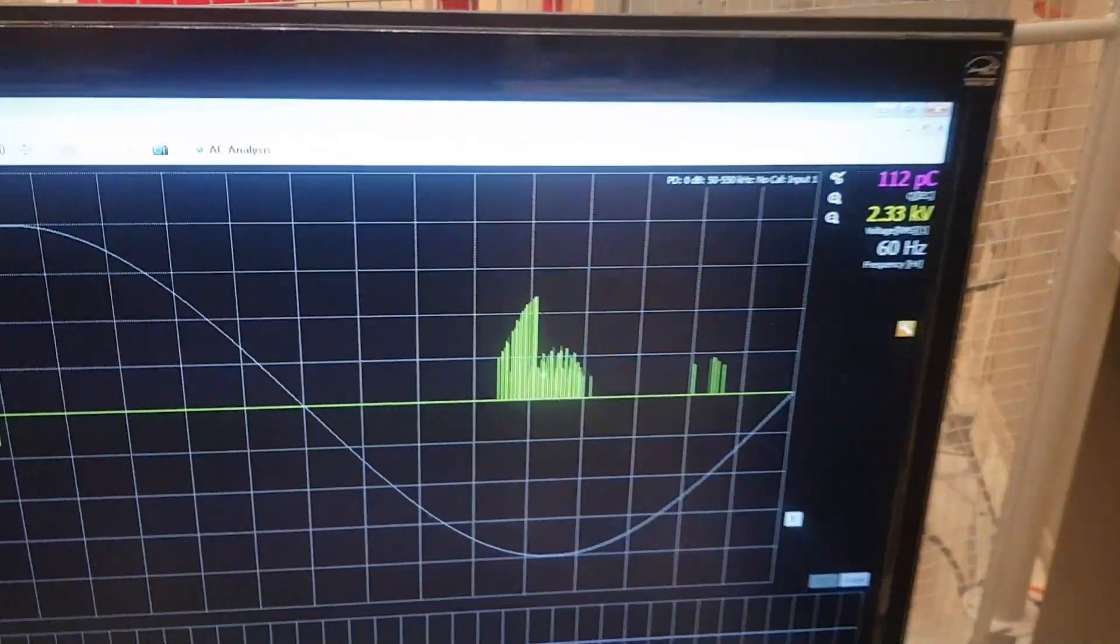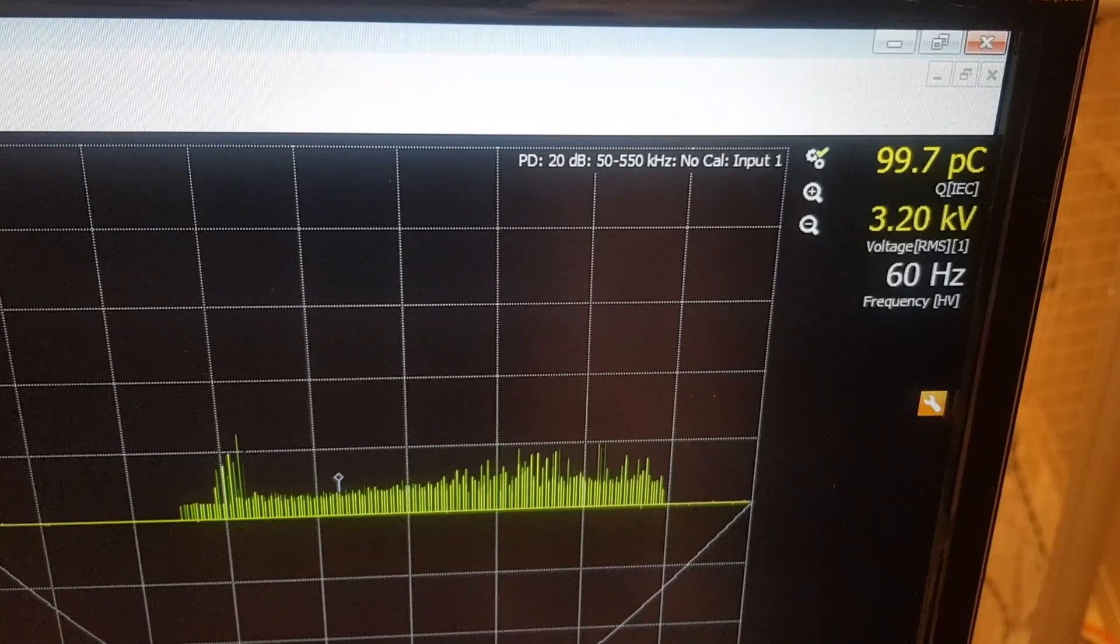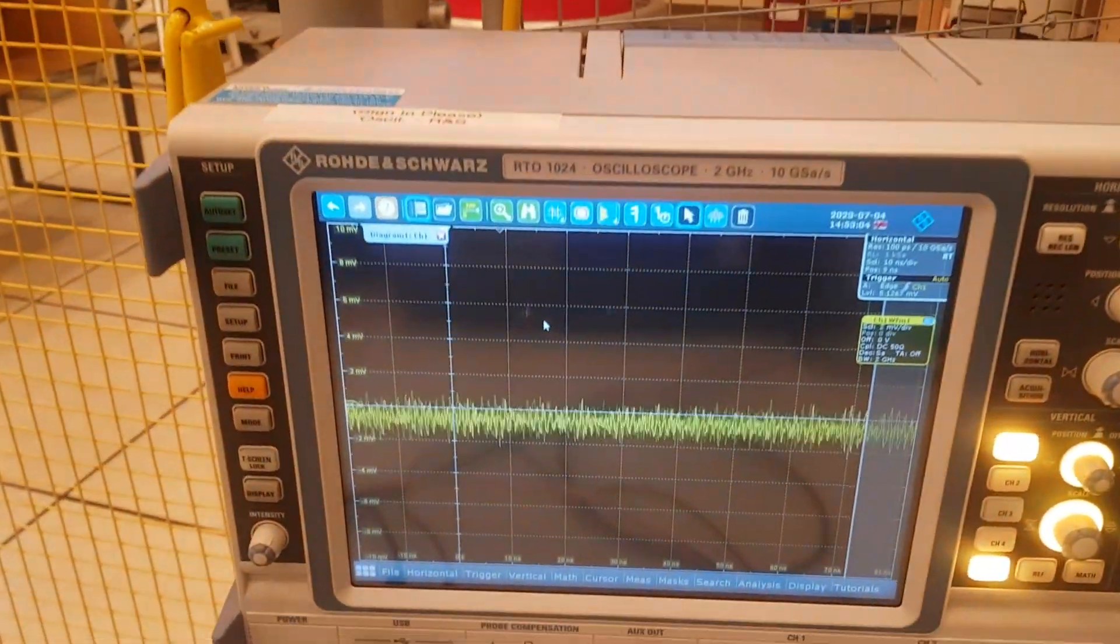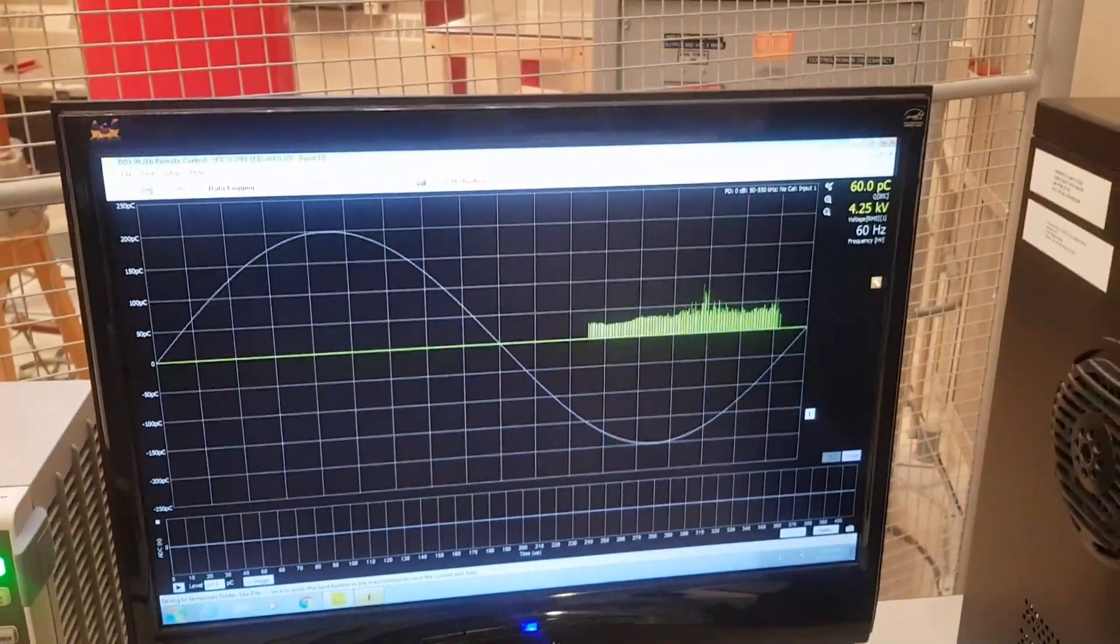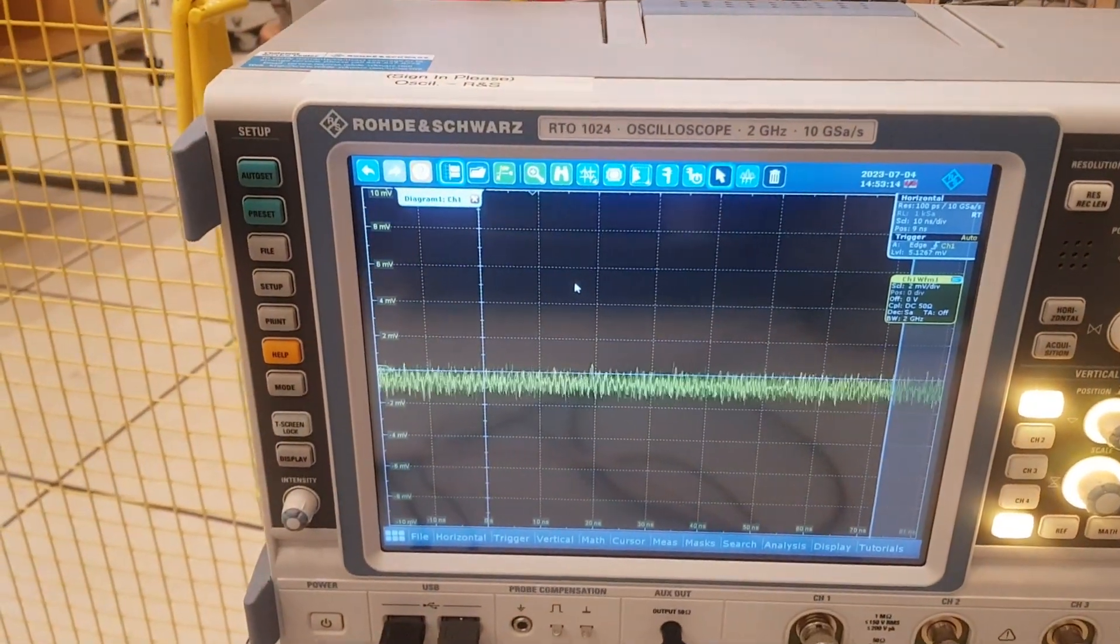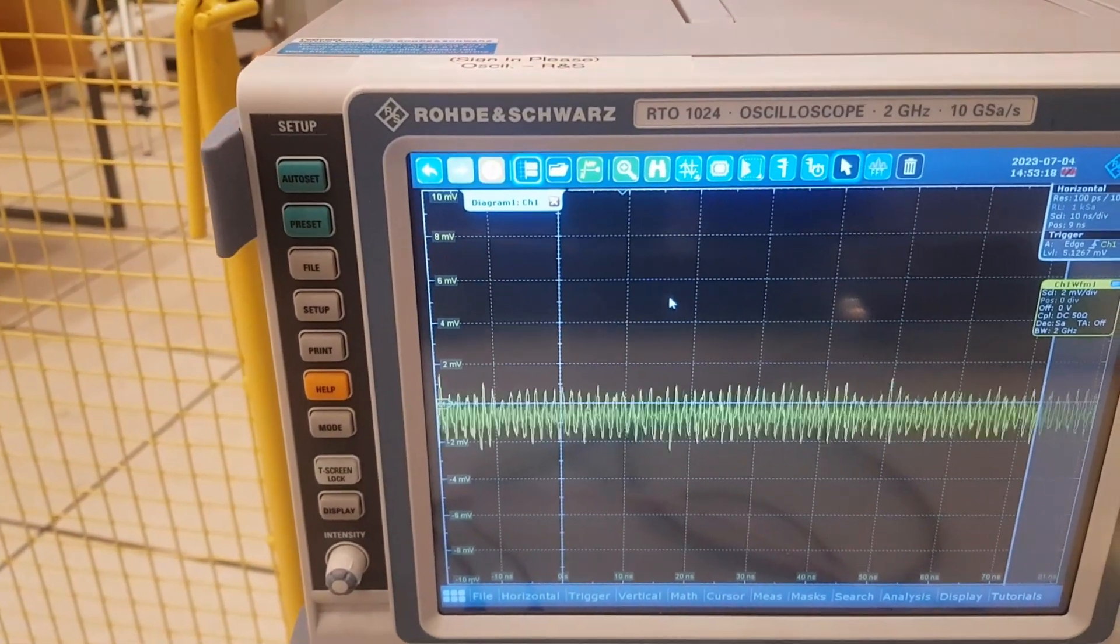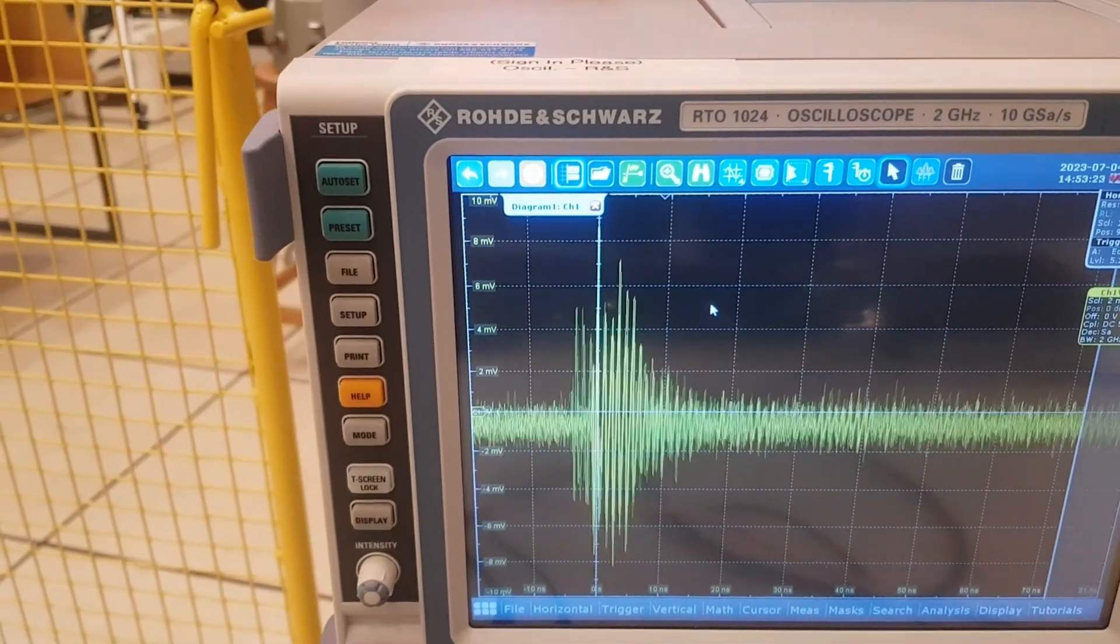Okay, so now we will start applying the voltage. And you can see here because of the sharp point, we have the partial discharge start to be detected at around three kilovolt. Now when you look here to the antenna, it still can't detect anything. What we'll do now, we'll start increasing the voltage until you start to see the pulses here. So the moment we start to see the pulses on the oscilloscope coming from the RF antenna, we will see at what voltage level it starts to detect that.